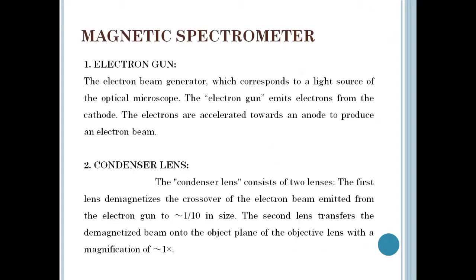The second part is the condenser lens, which consists of two lenses. The first lens demagnifies the crossover of the electron beam emitted from the electron gun to approximately 1/10 in size. The second lens transfers the demagnified beam onto the object plane of the objective lens with a magnification of approximately one.